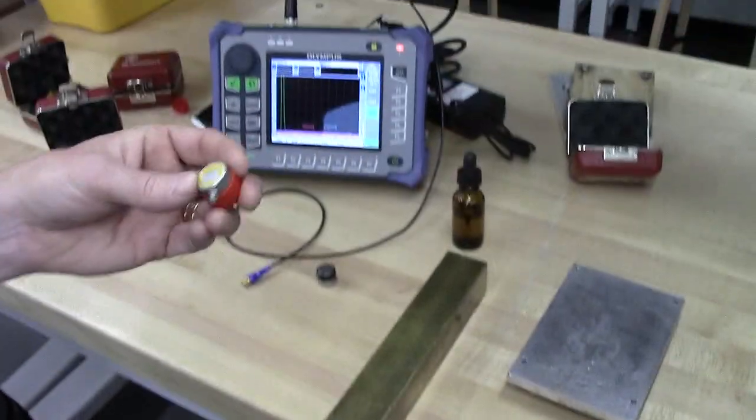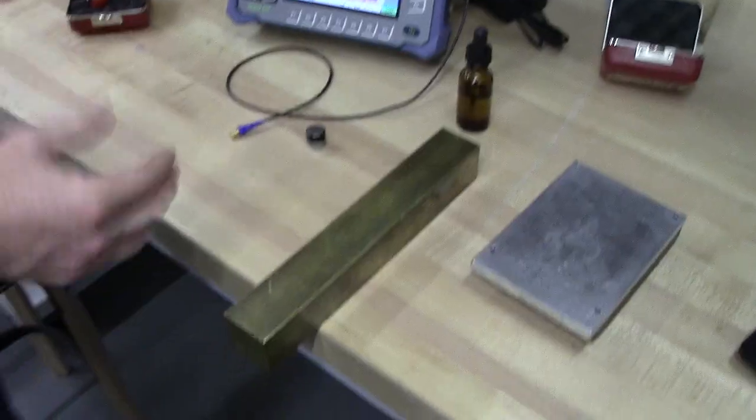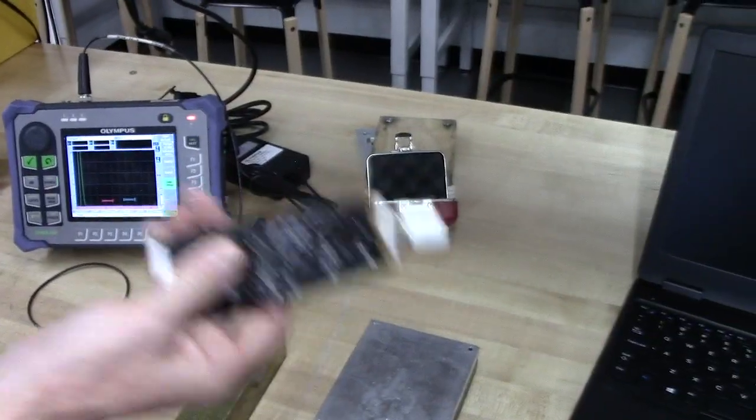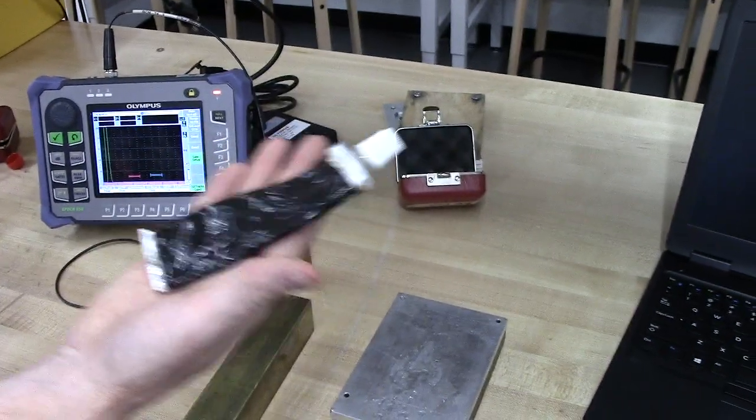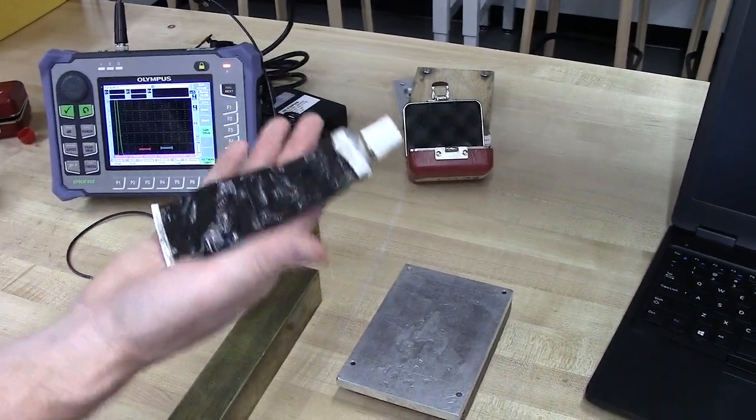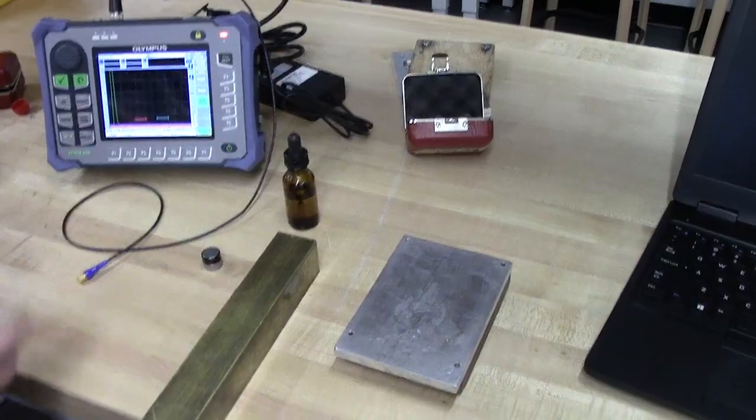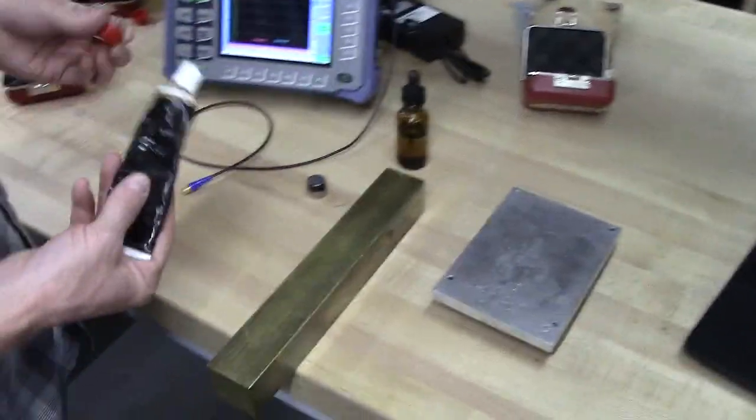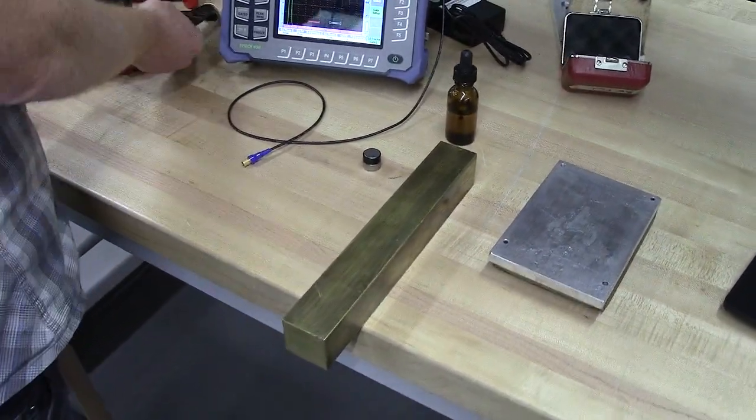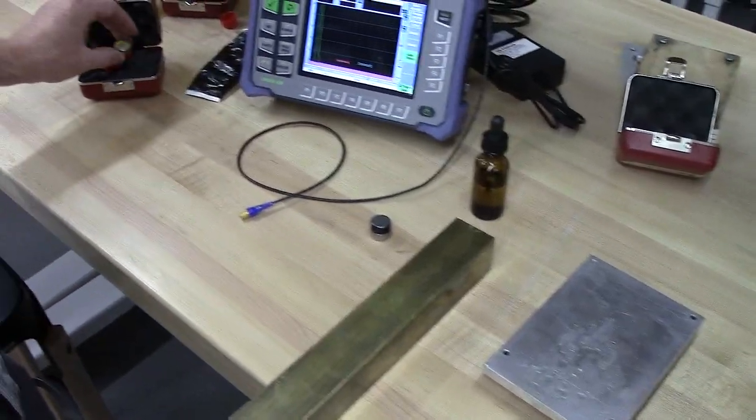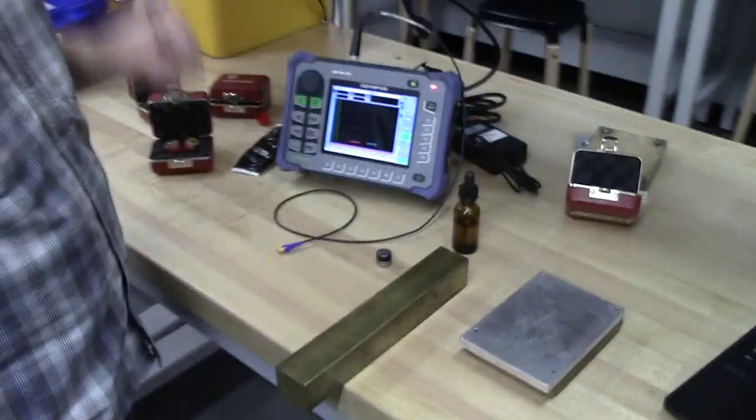So that's what this transducer does differently than this one. And for that, you'll need a different couplant. You need something, this is kind of more like molasses. It's shear wave couplant. It's water soluble so you can just clean it up with water and a paper towel. That's it. Good luck and we'll be there to help you if you have any questions.